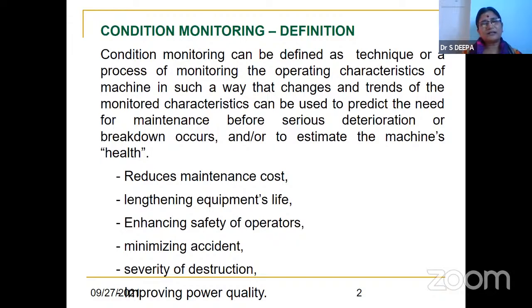Whatever disturbance there is in the machine will be reflected on the input side. Anywhere, we will have the supply, the drive, variable speed drives, the motor and the load. Wherever the fault is, we have to detect whether the fault is in the load, in the machine, in the drive or in the supply, without keeping a hand on the system. So automatic detection is the main thing. That is why we have to take up condition monitoring.